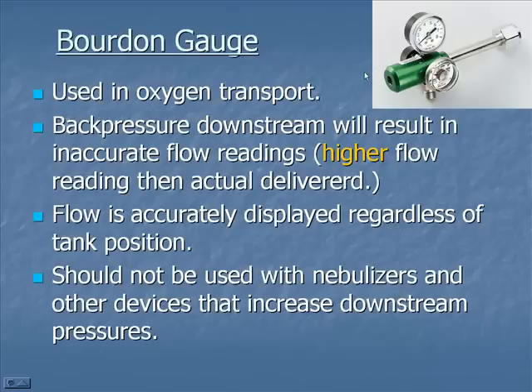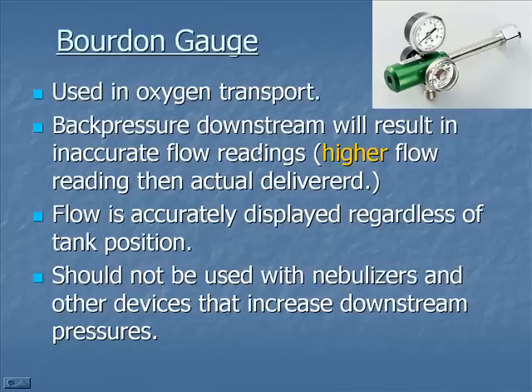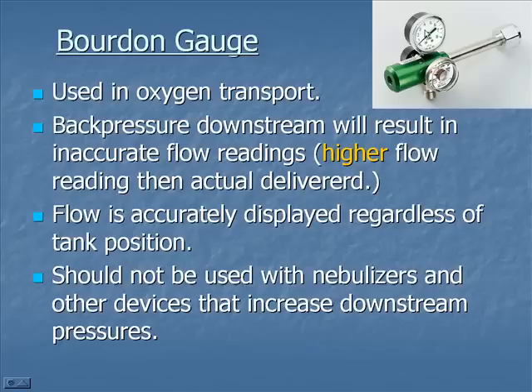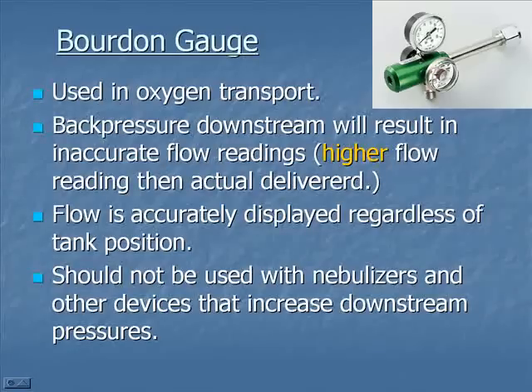Let's take a closer look at the Bourdon gauge. This type of gauge is primarily used in oxygen transport. Back pressure downstream will result in an inaccurate flow reading — if we cause an obstruction downstream, the flow reading on the gauge will read higher than what the patient is actually getting. So if I were to obstruct the tubing, I would want to know there's no flow, but this gauge can actually read higher. That's a disadvantage.